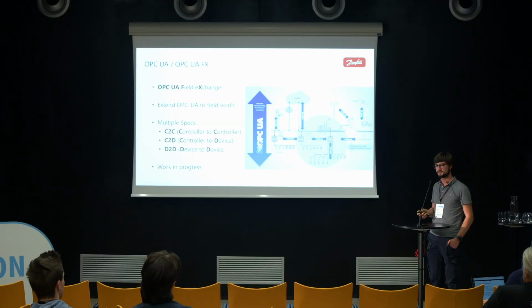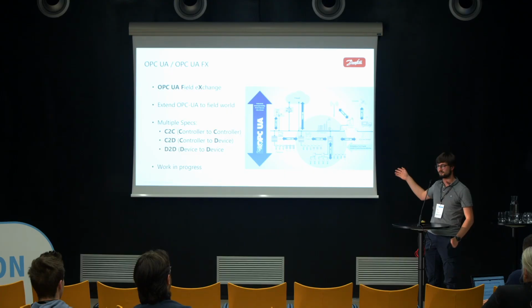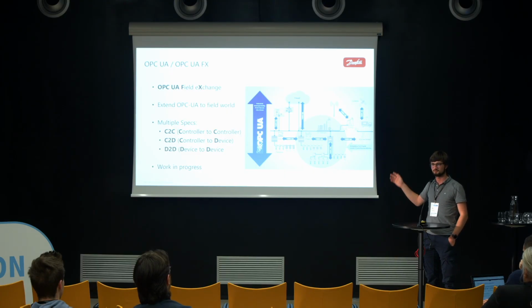As I said, this part already works, but it has a little problem. The normal OPC UA is not cyclic, so it's basically pretty indeterministic. You don't really have a guarantee about when your data arrives. It's also kind of slow if you are talking about the environments below. With OPC UA you're talking response times in the tens to hundreds of milliseconds, and they want to go much below that, because in the automation world we're sometimes talking about response times of under a millisecond.